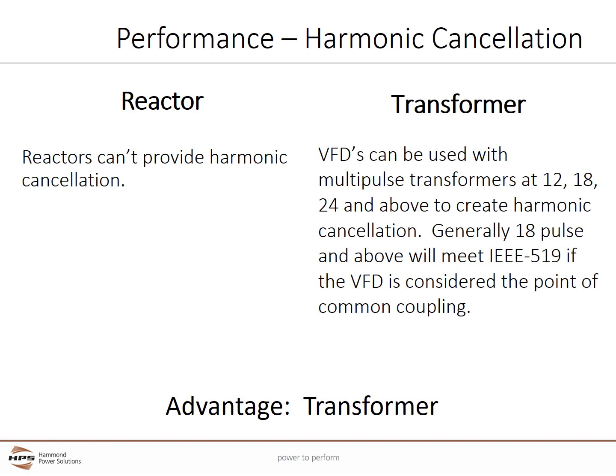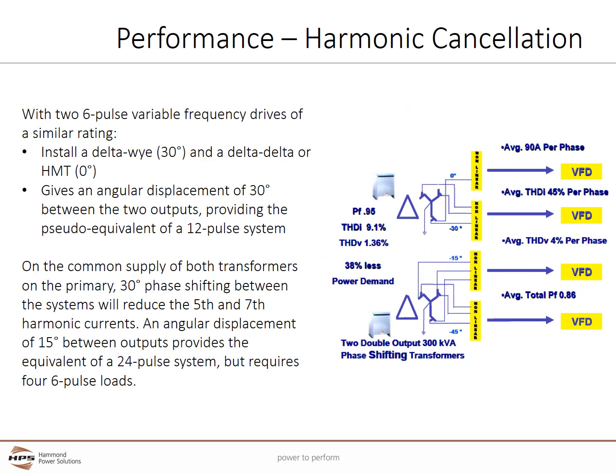By actually canceling out harmonic currents within the DIT's windings, better harmonic mitigation can be achieved than just with the reactor or base DIT. In fact, 18-pulse and higher DITs can often meet IEEE 519 distortion levels from when the VFD is considered the service entrance. While this isn't how IEEE 519 was meant to be applied, it can be an effective technique to improve power quality within a facility. Here is an example of how to make a pseudo 12-pulse application using 2 VFDs or groups of VFDs with nearly identical loads.